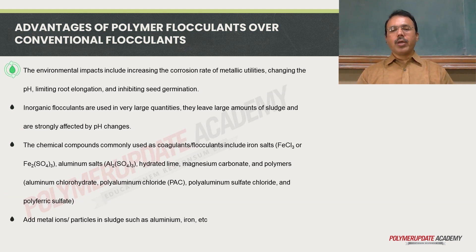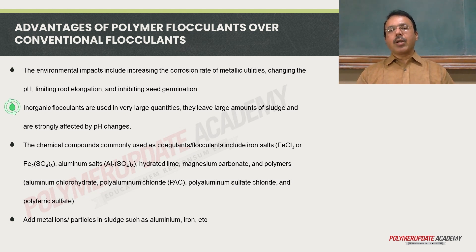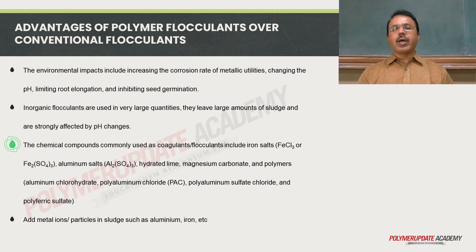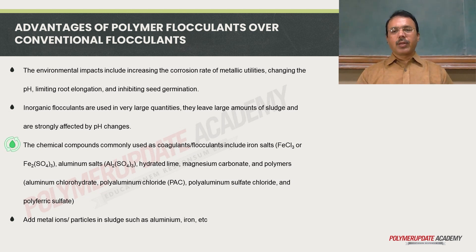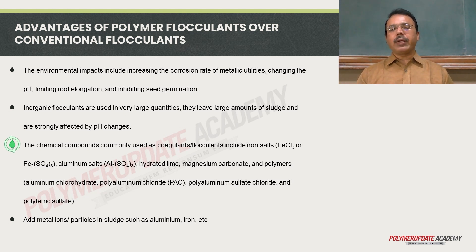The environmental impacts include increasing the corrosion rate of metallic utilities, changing the pH of water, limiting root elongation, and inhibiting seed germination in plants. Inorganic flocculants are used in very large quantities, leave large amounts of sludge, and are strongly affected by pH changes. The chemical compounds commonly used include salts of iron like FeCl₃ or Fe₂(SO₄)₃, salts of aluminum like Al₂(SO₄)₃, hydrated lime, magnesium carbonate, and polymers like aluminum chlorohydrate, polyaluminum chloride, polyaluminum sulfate chloride, and polyferric sulfate.